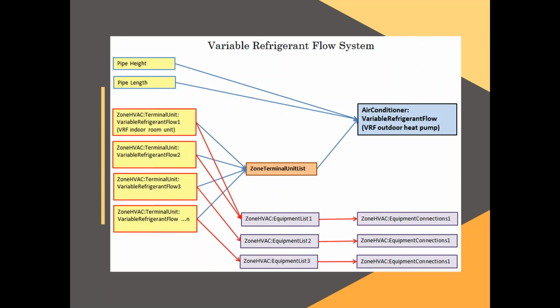This is an example of some of the detailed information that the GUI allows you to not think about, but I wanted to just touch on it because it's helpful to know what's going on behind the scenes, so to speak. Within EnergyPlus, as Matt was sharing, the outdoor unit, or the heat pump, is sort of the heartbeat, the main energy mover for a VRF system, but that air conditioner or heat pump is connected to a multitude of indoor terminal units. Within EnergyPlus, you describe the terminal units, and those would be the zone devices that David just mentioned. Each of those terminal units has to be assigned to a terminal unit list, which is the list of terminal units that are attached to an air conditioner unit.